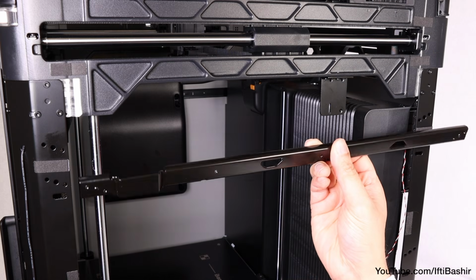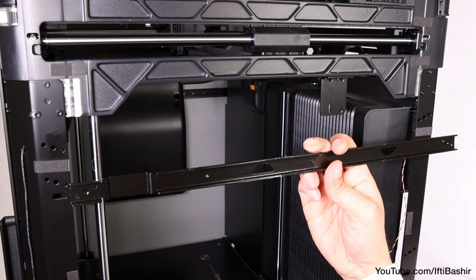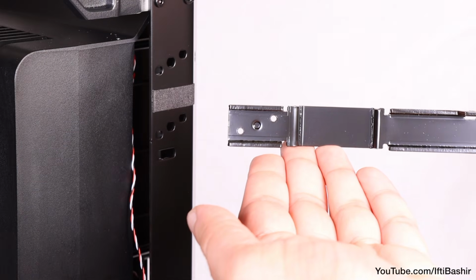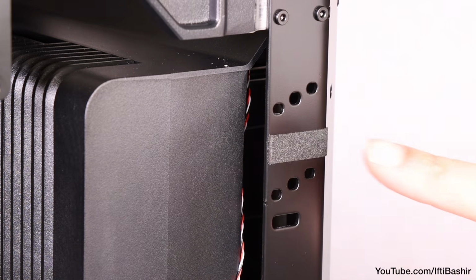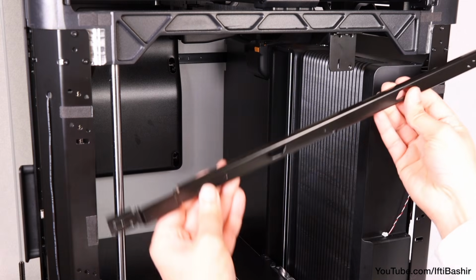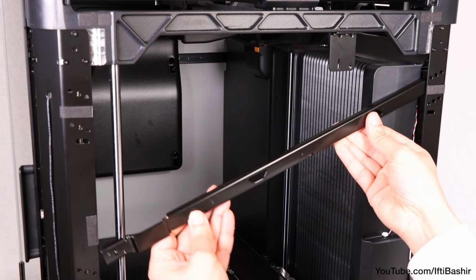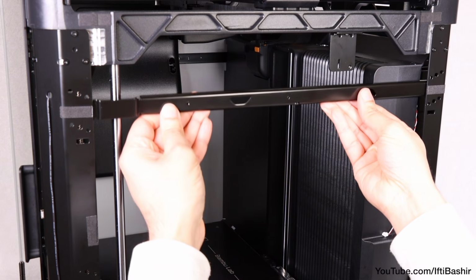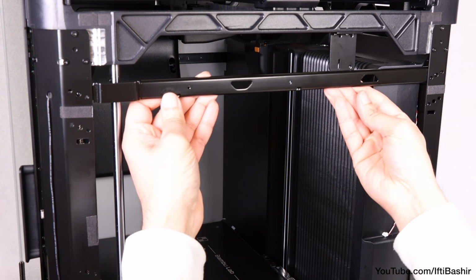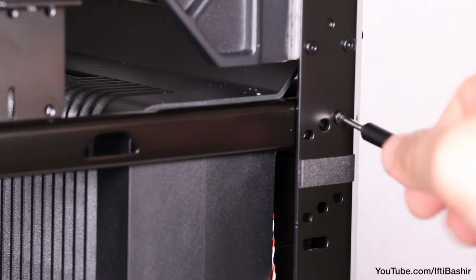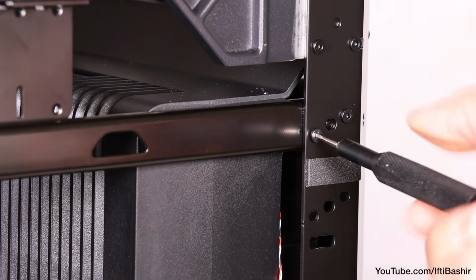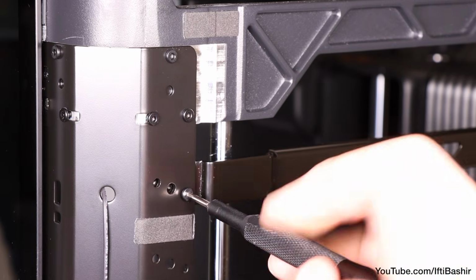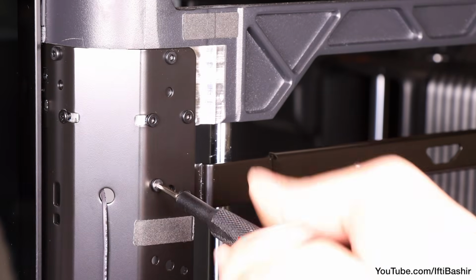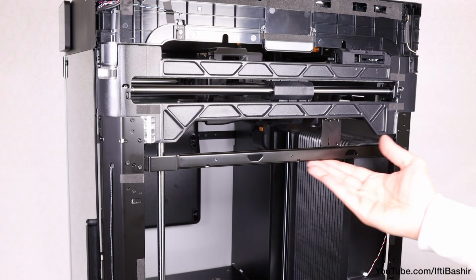Once in place, we're ready for our first rack mount beam. Notice the holes on either end of the beam. These line up with the holes in the existing frame, so tilt the beam so that the ends sit behind the frame and straighten until the holes line up between both beam and frame, before using 2 M3x6 screws to secure, and repeating the same on the opposite side. That's our first beam installed.